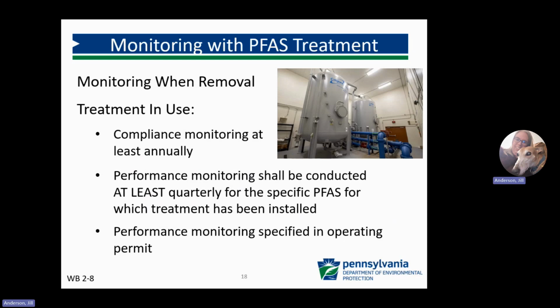For systems that have PFAS removal treatment, compliance monitoring for the specific PFAS for which treatment has been installed must be done at least annually. And whether it's annually or quarterly will depend on whether the target PFAS is reliably and consistently below the MCL. Performance monitoring for the specific PFAS for which treatment has been installed will be done at least quarterly, and all performance monitoring requirements will be specified in the operating permit special conditions.